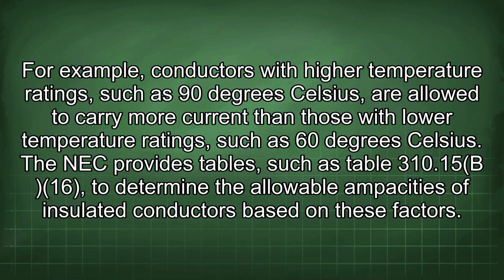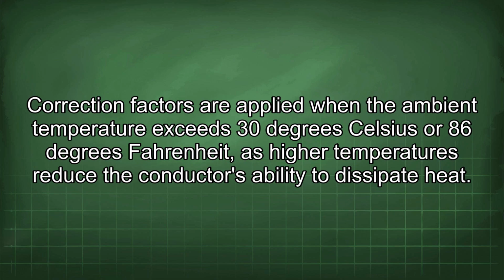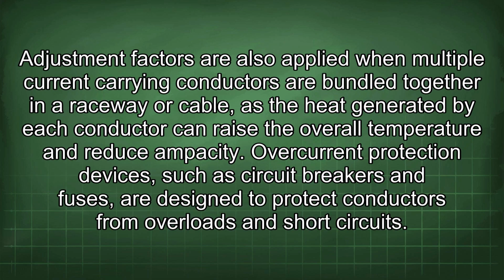The NEC provides tables, such as Table 310.15(B)(16), to determine the allowable ampacities of insulated conductors based on these factors. Correction factors are applied when the ambient temperature exceeds 30 degrees Celsius or 86 degrees Fahrenheit, as higher temperatures reduce the conductor's ability to dissipate heat. Adjustment factors are also applied when multiple current-carrying conductors are bundled together in a raceway or cable, as the heat generated by each conductor can raise the overall temperature and reduce ampacity.